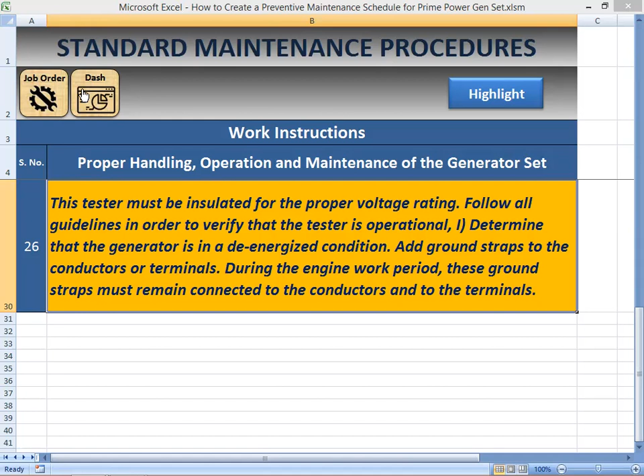So determine that the generator is in de-energized condition. Add ground straps to the conductor's terminal during the engine work period. This ground strap must remain connected to the conductors and the terminals. Okay, that's all about the work instruction or standard operating procedures when you are performing the maintenance procedure of the generating sets. Okay, I think I have presented everything here.